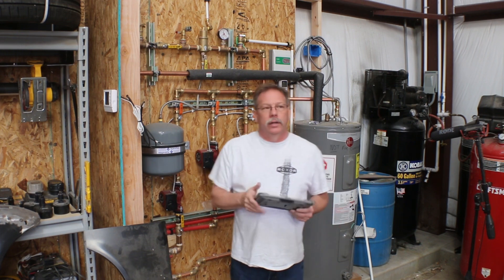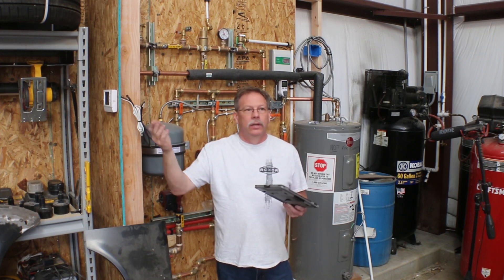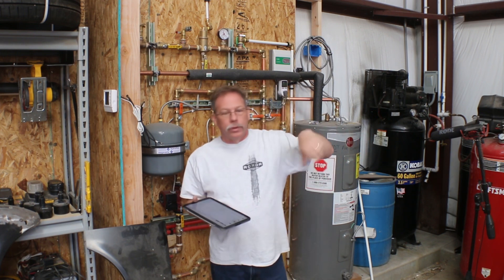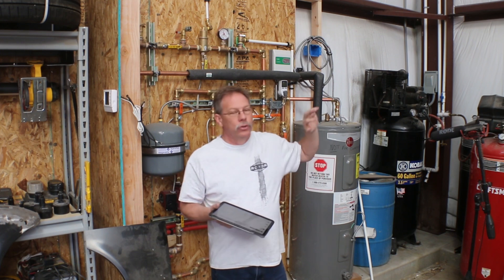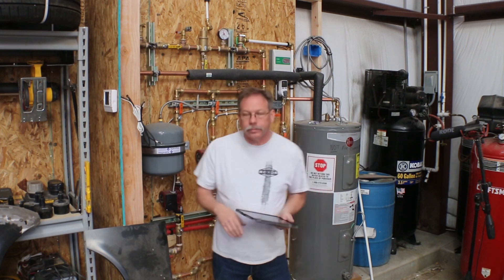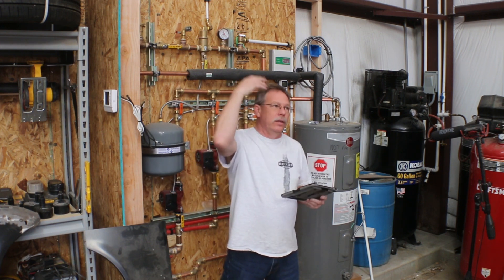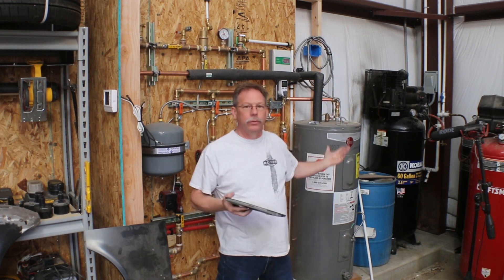The system will use evacuated tube solar panels — hydronic, not PV — just for heating the shop. The large storage tank with extra coils means that during summer, when our climate is still fairly cool well into the season, we can transfer that heat to our swimming pool that the grandkids use, heating it earlier in the year and extending the season later into fall. So the system will work two ways — the shop loop will have antifreeze, the panels will have antifreeze, and we can cycle pool water through one of the other coils.